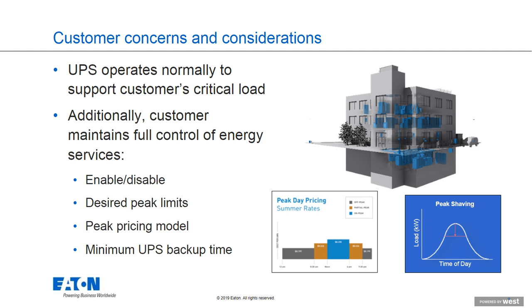Customers will have some concerns and considerations about operating in this mode. For decades, the idea behind a UPS has been that it's dedicated to supporting the data center and nothing else, because that's so important. That remains true. However, we have to design and operate with an eye toward cost, and if it's possible to maintain the UPS's primary function—5 minutes of battery backup at typical operating load—that needs to be held sacred and constant no matter what else we use the UPS for.